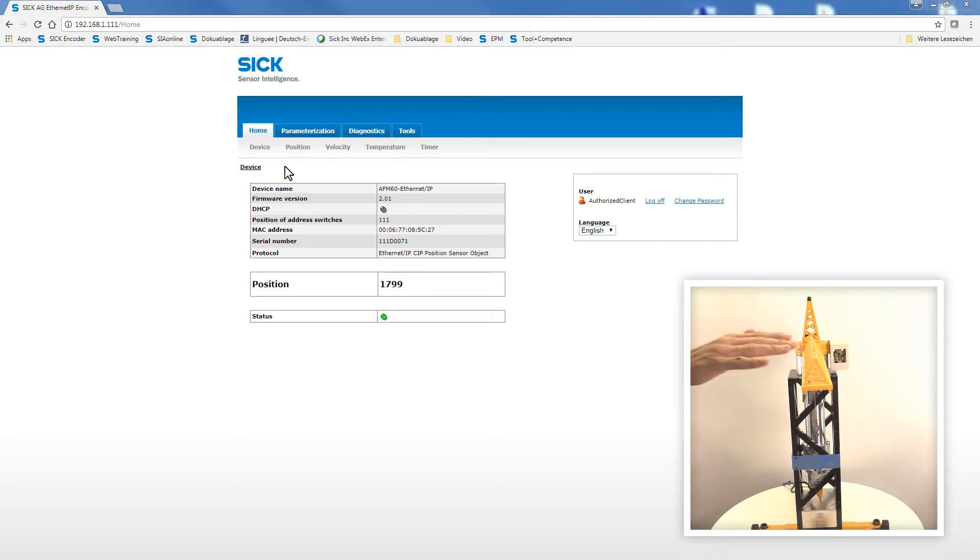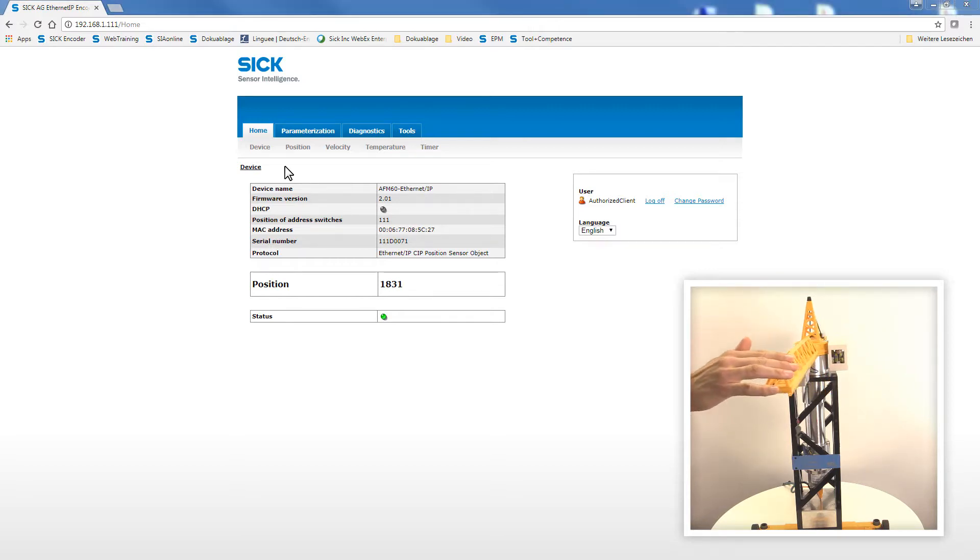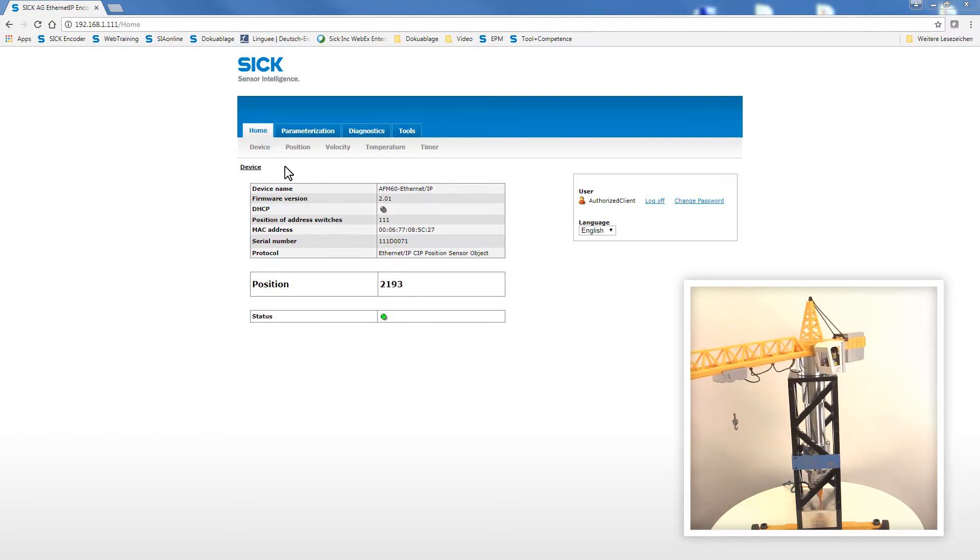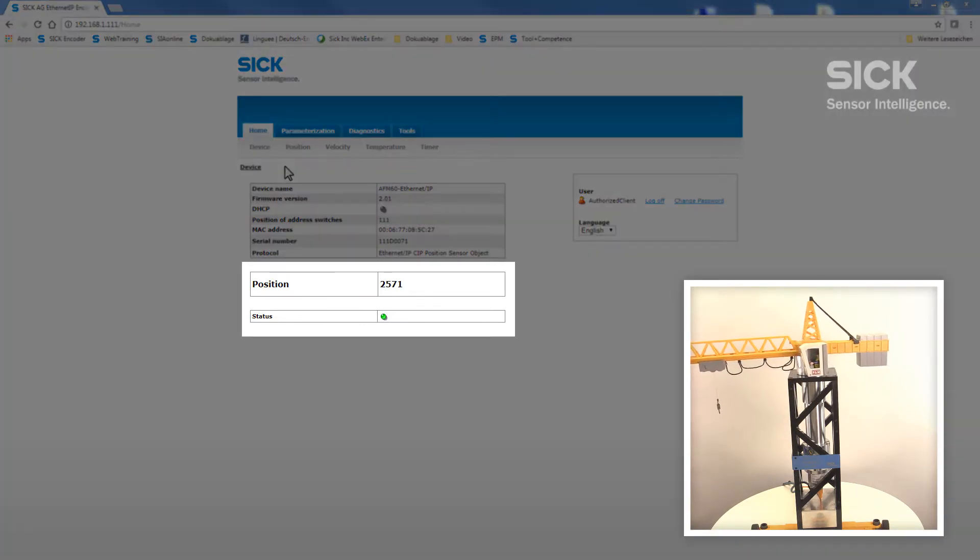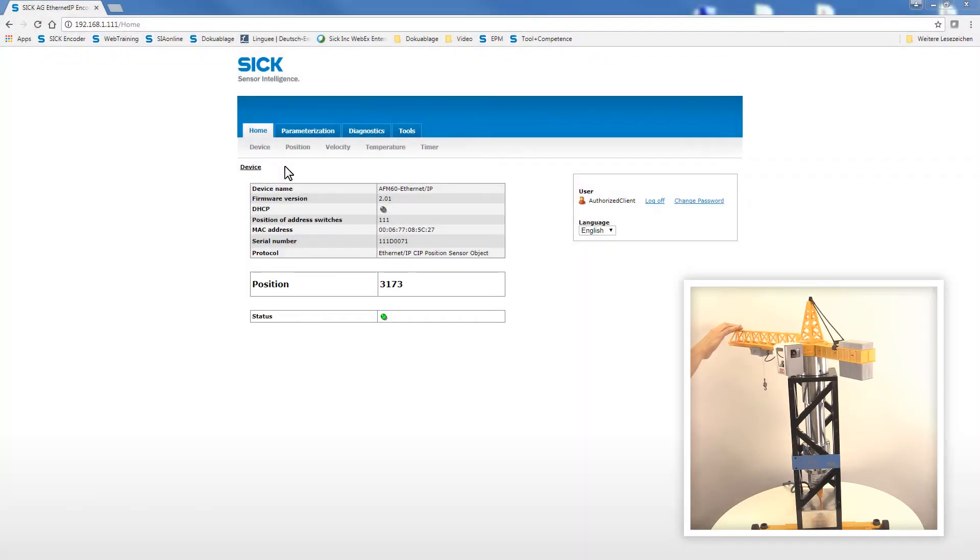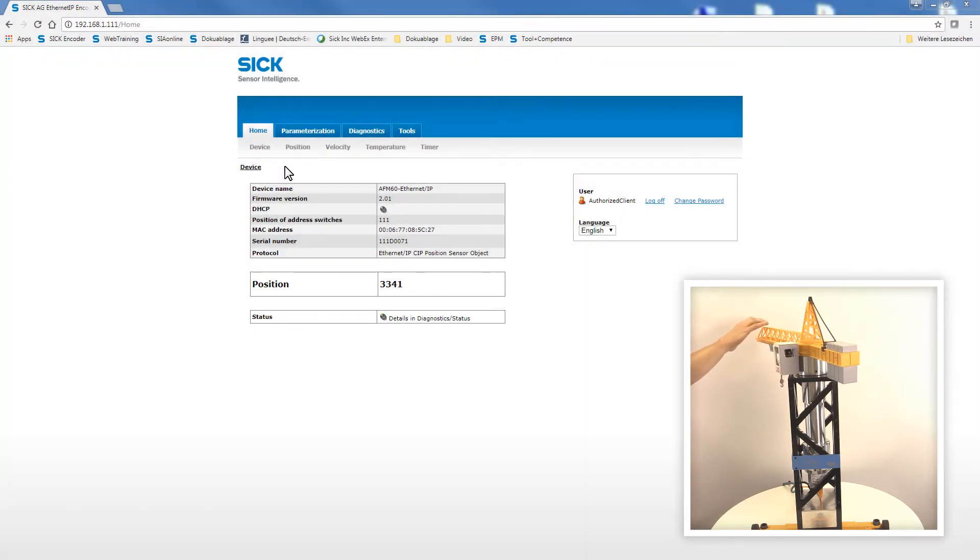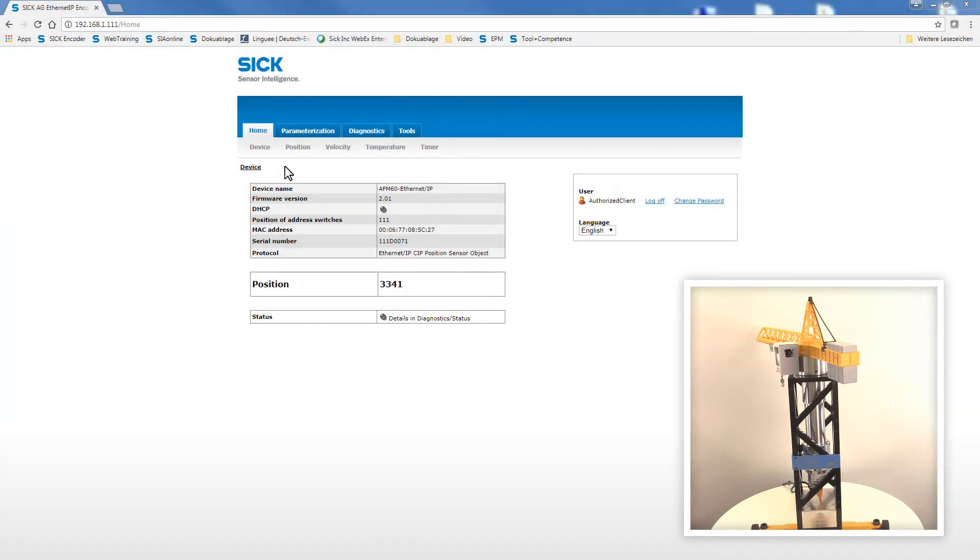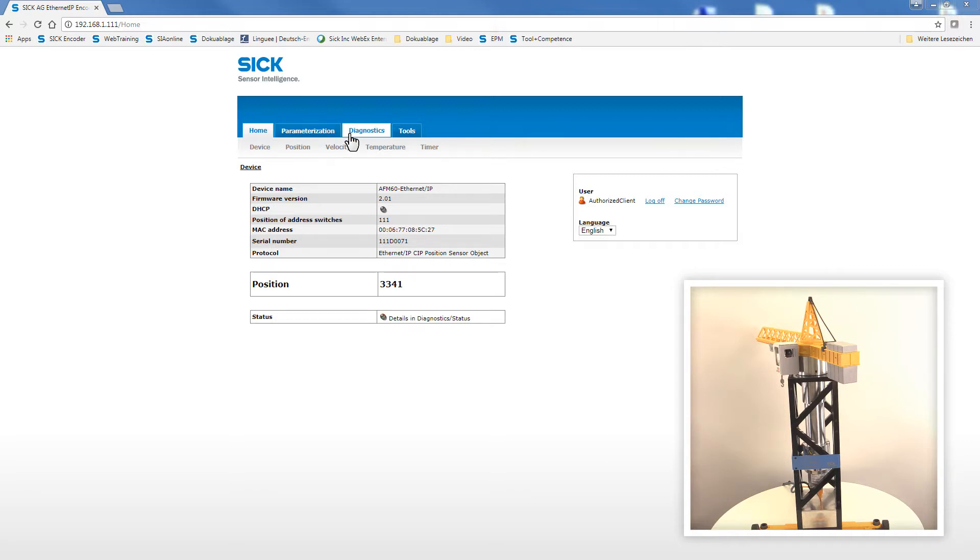Here, we slowly start turning the boom in clockwise direction. As we are turning the boom, the position values are increasing. As soon as we have exceeded the upper position limit of 3300, the status indicator will switch to red blinking. This indicates a warning signal while the encoder remains in operation mode. In addition, a short message is displayed: details in diagnostics status.